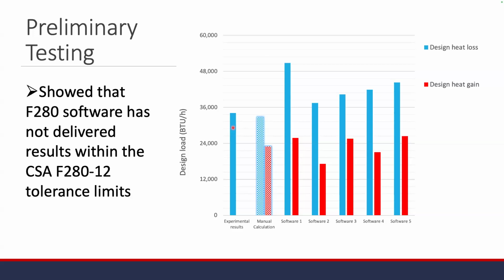They then also did some experimental results. I believe this is based on the CCHT house that NRCan has, the Canadian Centre for Housing Technology - they have a pair of identical houses, and it's one of the drawings we use in the testing protocols. They have all sorts of metering and gauges and stuff like that. So they did a manual calculation and then actually monitored the house, and at design conditions it's using - I forget my scales here - about 30,000 BTU heat loss, and the actual experimental data, or clocking of the gas meter or whatever they did, came in at around 33,000. So pretty good alignment there.